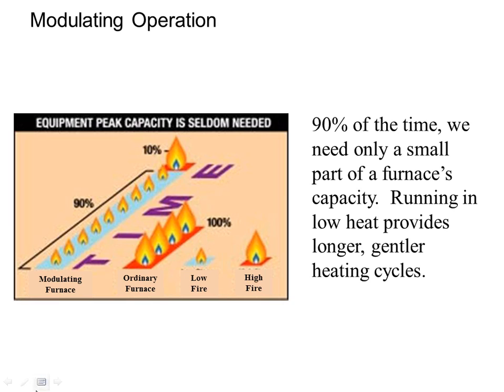So how would I give you a little furnace inside the big furnace was kind of the idea or the selling strategy. So that way, when it's 30 degrees outside, only the little furnace runs. When it's 0 outside, the big furnace runs. Well, the same thing happens with this modulating story, except for now, you're going to get 61 furnaces, right? So I got a furnace for every single outdoor air temperature that you'd have. No matter what the temperature is, I know which furnace I'm going to turn on for you, and it's all going to be inside one furnace box, and it's just going to give you the exact amount of BTUs you need on that given day.